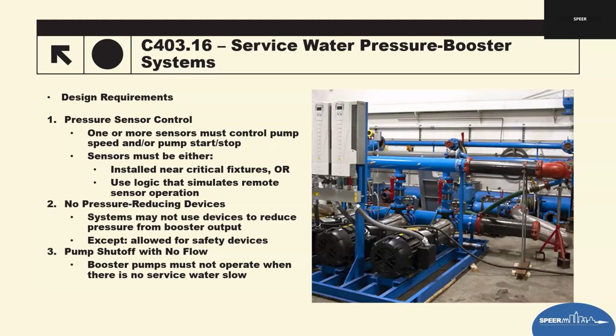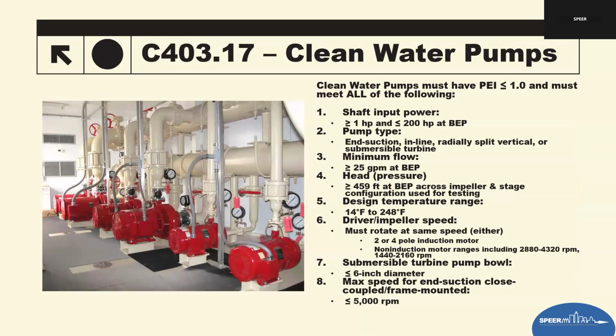Test the system to confirm pumps reduce speed or shut off at low flow or no flow. Ensure no unauthorized pressure reducing valves are installed, and then confirm VFDs are operational and tied to building controls.